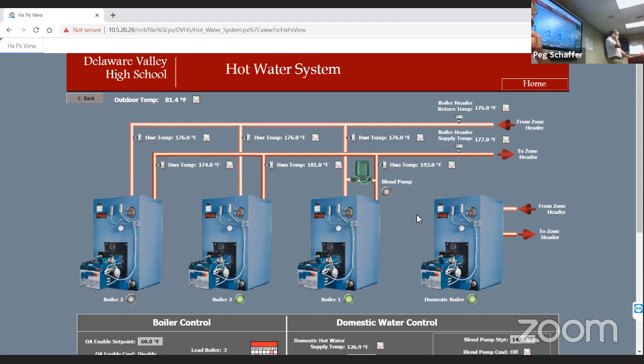Okay, so that's how we're providing the heat, through water. It's a conversion from gas through a heat exchanger to water, and then the water flows to provide heat to the unit ventilators, rooftops and such. From an air conditioning standpoint, each classroom has rooftop air conditioning units. They're small condensing units, basically direct expansion, and they provide air conditioning to each unit independently. So while the boiler plant is more of a global thing, providing heat to all the rooms, each room has its own specific air conditioning unit. Like I said, there are so many different pieces, because the middle school is a little bit different. Each building is slightly different, but that's the gist of the high school when it comes to the heating and the unit ventilators.